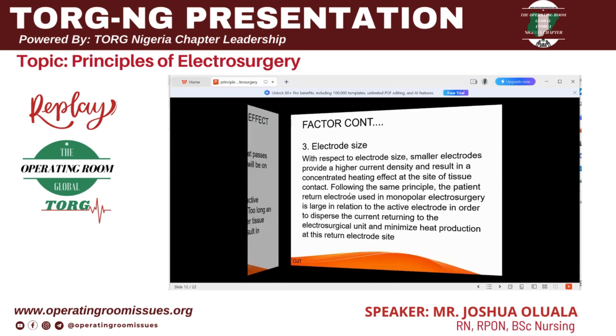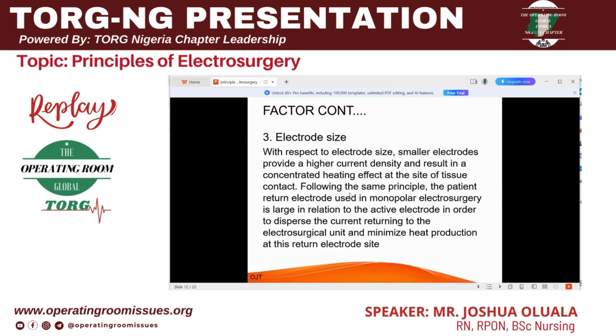Well, the third factor is the electrode size. So we said with respect to electrode size, smaller electrodes provide a higher current density and result in concentrated heating effect at the site of the tissue. Take for example, in pediatric surgery, when we are operating on neonates, we actually want this diathermy, this pin tip, because we don't want any spread. We just want the heat to be concentrated. The diathermy tip for neonate is actually like a needle point. So once we put it, you don't want it to spread, unlike the normal conventional diathermy tip.